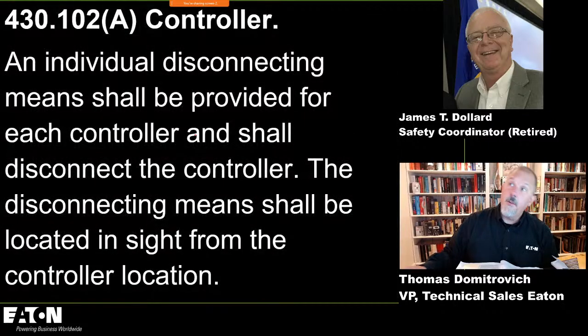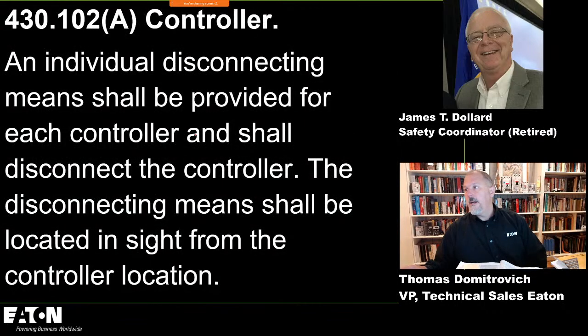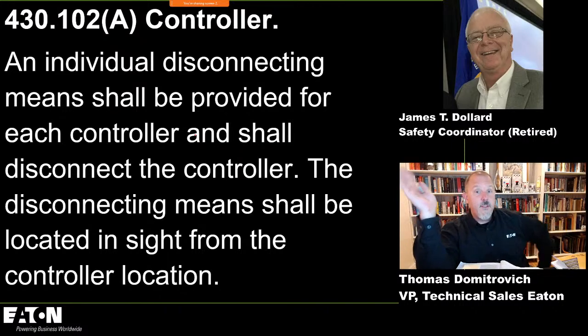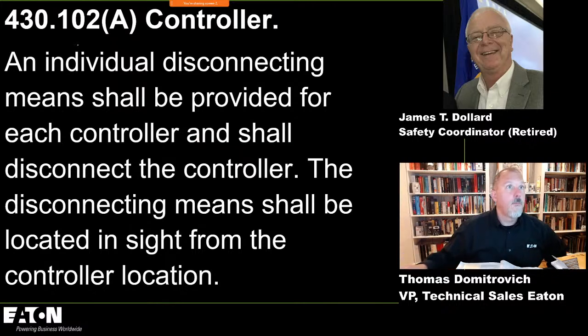Then I went back to 430, so I bounced around a little bit. This is talking about disconnecting means. So back in 430, we have different requirements for disconnecting the motor, right? Yeah, and that was many cycles ago. I remember because later in your slide deck here, there's a requirement for a disconnect within sight of the motor. And that was a fight. That took a couple of cycles, but we finally got it.